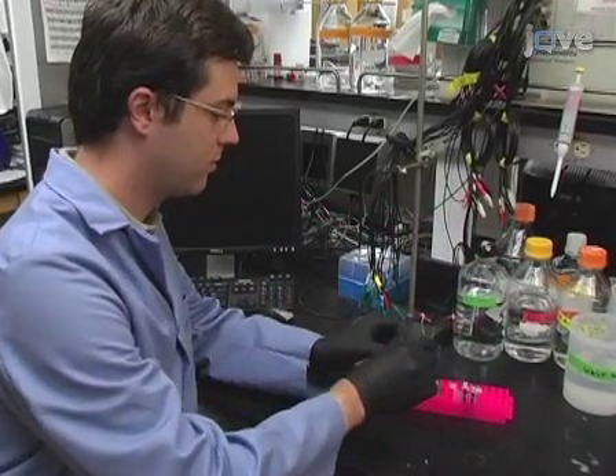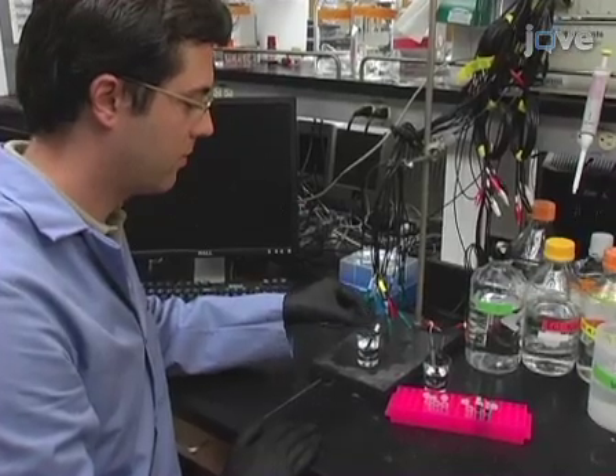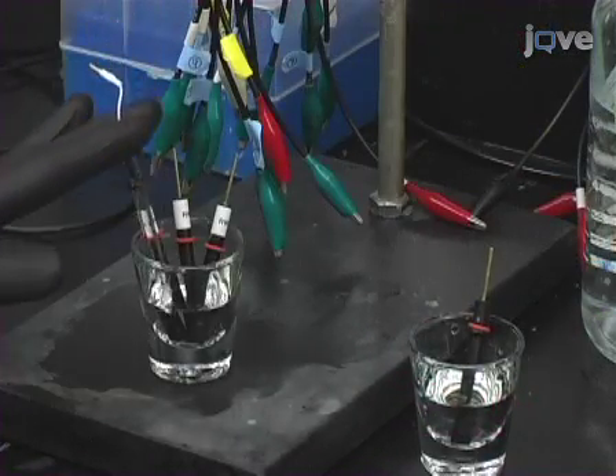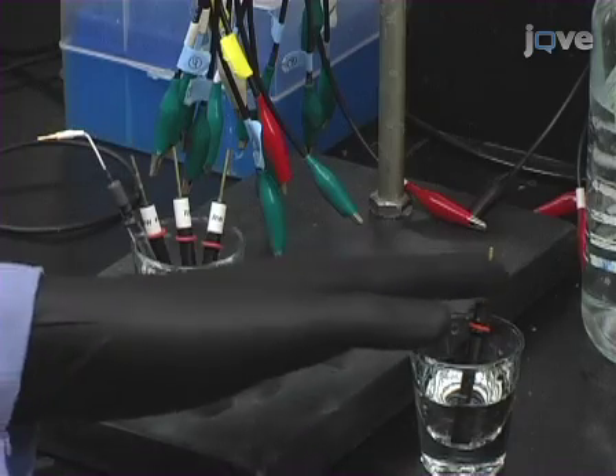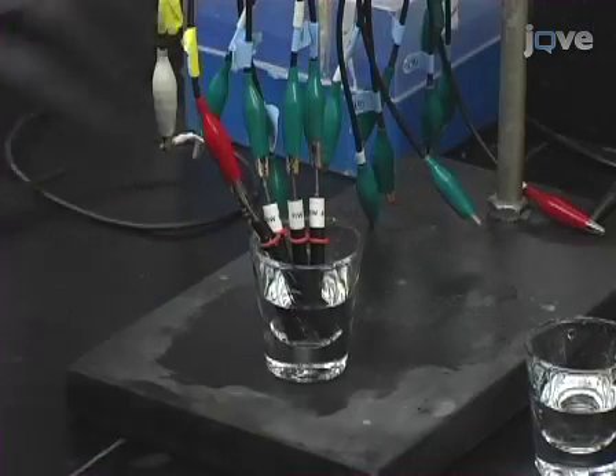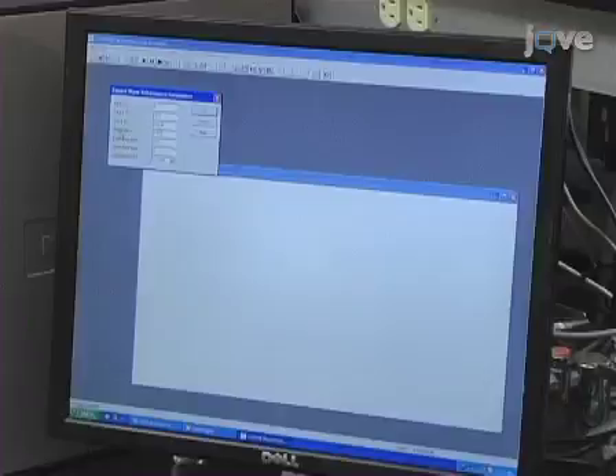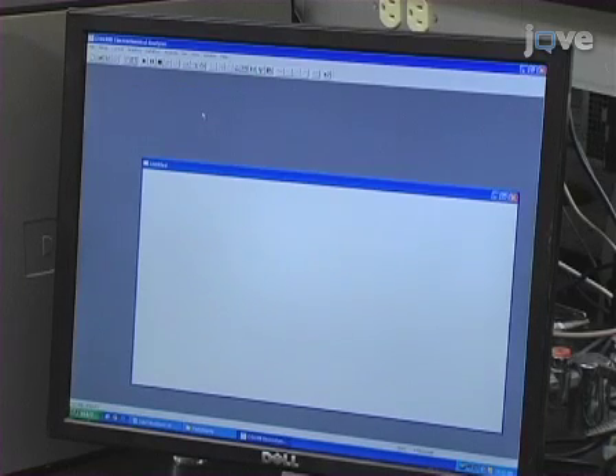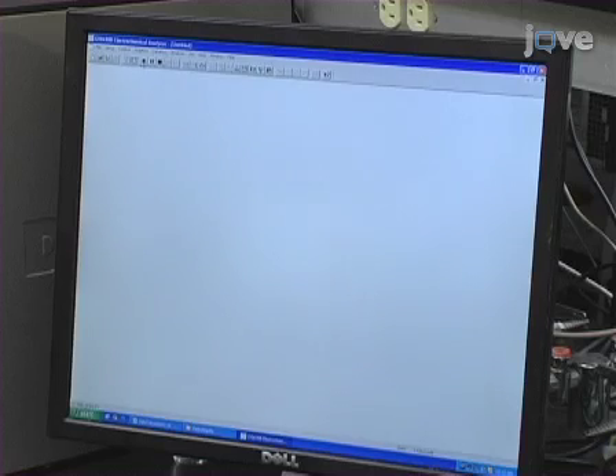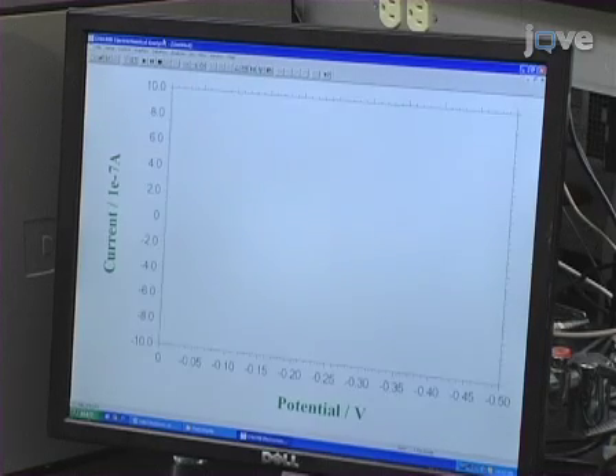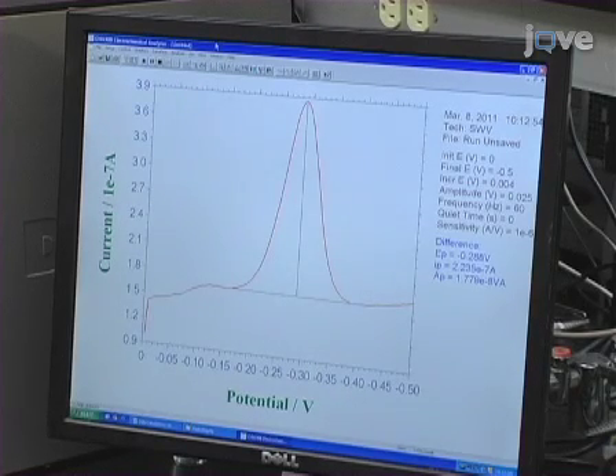Next, place the sensor in the relevant blank solution and place a platinum counter electrode and a silver chloride reference electrode into the solution. Attach the electrodes to the potentiostat. Perform square wave voltammetry as described earlier. The optimal square wave frequency for the particular probe architecture used in this example is 60 Hz. A rounded peak should appear around negative 0.25 volts. Save this background measurement.